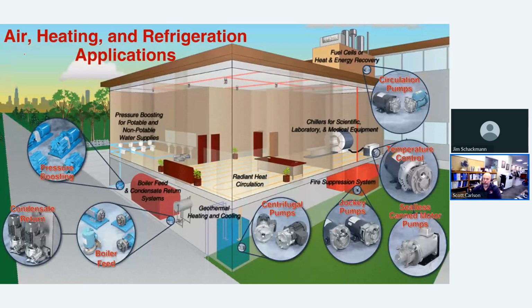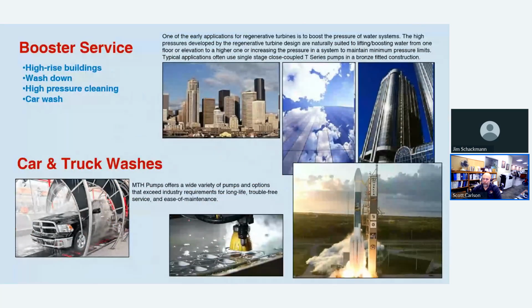So when we look at our applications here, we have air, heating, and refrigeration applications. There's just a different diagram that shows the different places that you can find regenerative turbine pumps. We'll go over each of those here. The first one is in booster service. Anytime you need to move fluid up multiple stories or boost the pressure of fluid that goes from city pressure to a higher pressure, or whatever the source may be, regenerative turbine pumps are ideal for that because they can increase that pressure without necessarily increasing the flow.